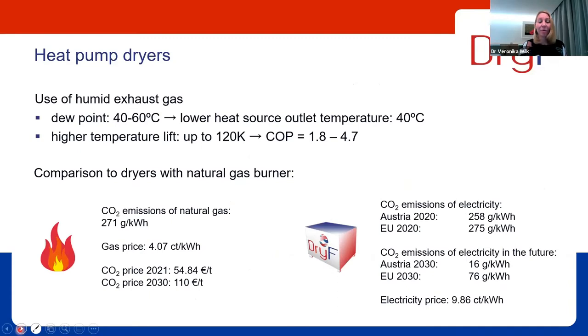And now I want to take the operation results from the DryFiciency demonstrators to speak about the potential of drying in general and how to use heat pumps for drying. So as I've said, we have very warm heat sources in both our demonstration installations. They are both external heat sources, not directly related to the dryer. For the Wienerberger installation, it's the absorption heat pump. And at the Agrana installation, it's that waste heat recovery cycle that collects waste heat from other processes that are available.